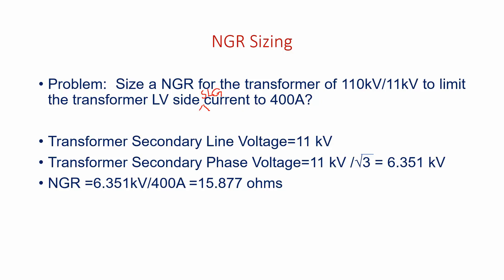So NGR is calculated simply as secondary phase voltage divided by the amount of current to be limited in the secondary side of transformer single line to ground fault, that is 400. So 6.351 divided by 400 is 15.877 ohms. Your NGR value is 15.877 ohms.